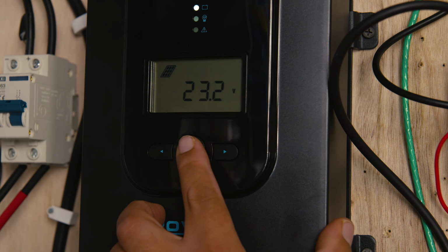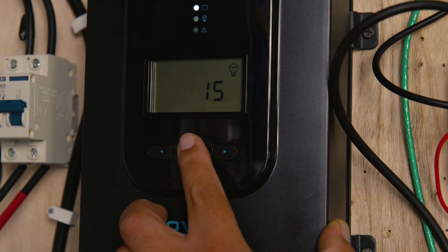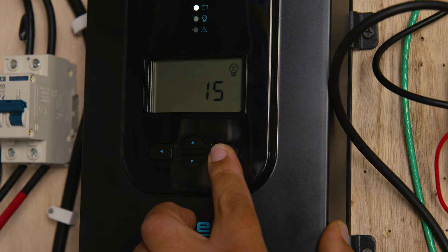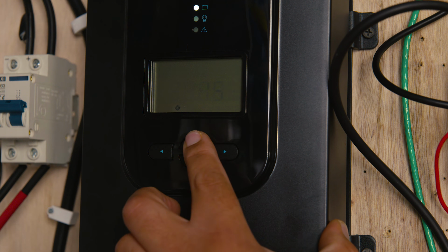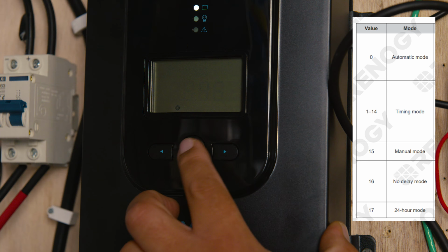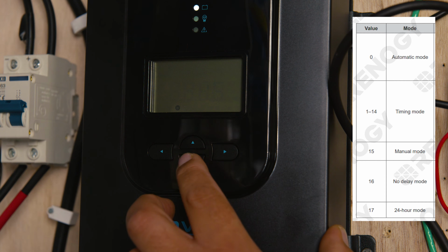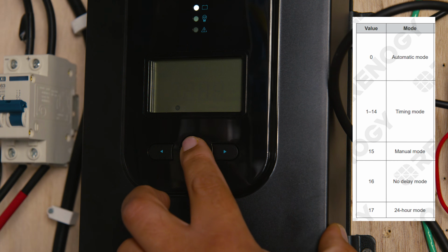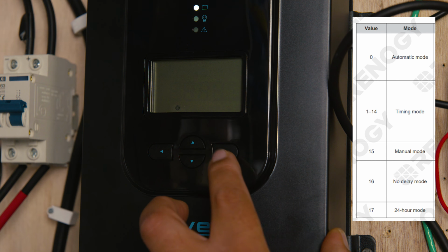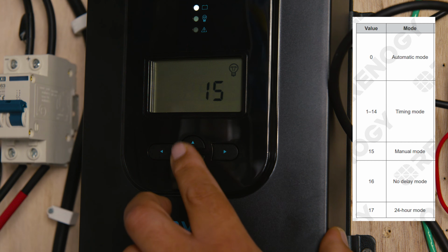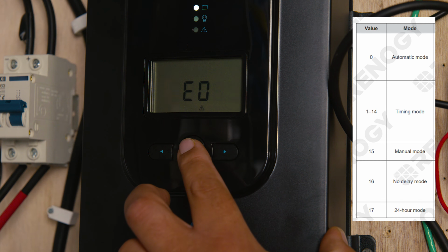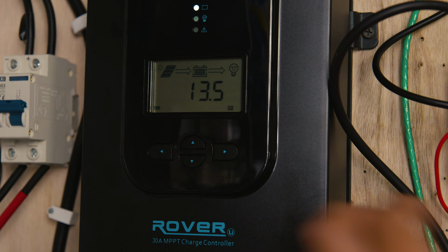If you want to change your load settings or values, go to the load screen and hold the right arrow button for a minimum of 3 seconds. It's going to start blinking. Then with the up arrow or down arrow, you can change it to your desired value. 0 is automatic mode, 1 to 14 is timing mode with durations in hours for each number, 15 is manual mode meaning the right arrow button when pressed turns it on and off, 16 is no-delay mode, and 17 is 24-hour mode.